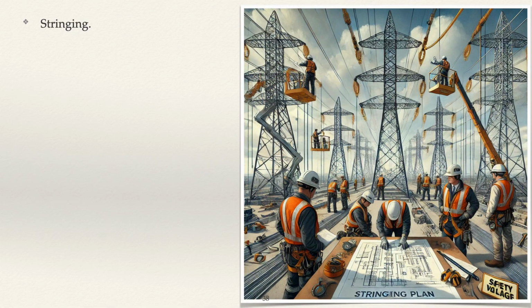G. Stringing. The purpose is to ensure that the conductors, earth wires, and optical ground wires are installed and tensioned correctly between towers. The inspection focus on 1. Paying out conductor, earth wire, OPGW, ensuring that the conductors and wires are properly handled and installed without damage.